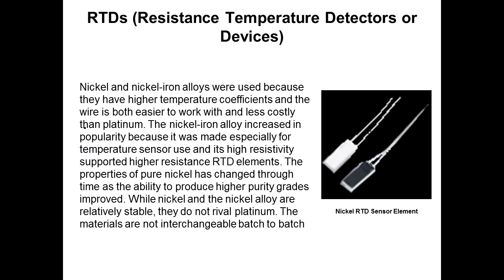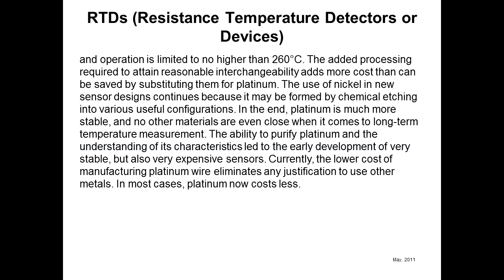While nickel and the nickel alloy are relatively stable, they do not rival platinum. The materials are not interchangeable from batch to batch, and operation is limited to no higher than 260 degrees C. The added processing required to attain reasonable interchangeability adds more cost than can be saved by substituting them for platinum. The use of nickel in new sensor design continues because it may be formed by chemically etching into various useful configurations. In the end, platinum is much more stable, and no other material can even come close when it comes to long-term temperature measurement.